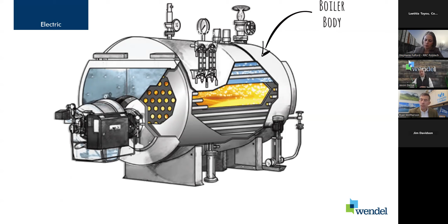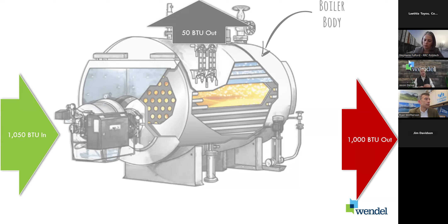Well, let's say we wanted to put an electric boiler in. Well, we can get rid of that burner. We just have the boiler body at that point. And to get that 1,000 BTUs out, I only need to bring in about 1,050 BTUs. I'm not combusting anything anymore at the source. I only have about 50 BTUs of loss. So electric boilers by their nature are actually more efficient than natural gas boilers. But they're still using about 1,000 BTUs of input energy.